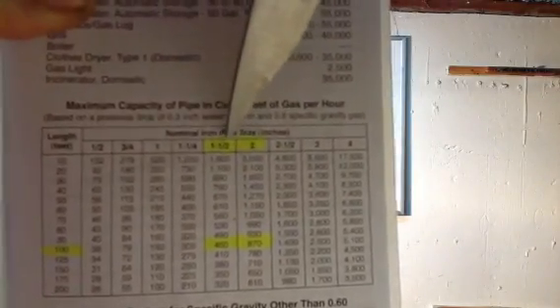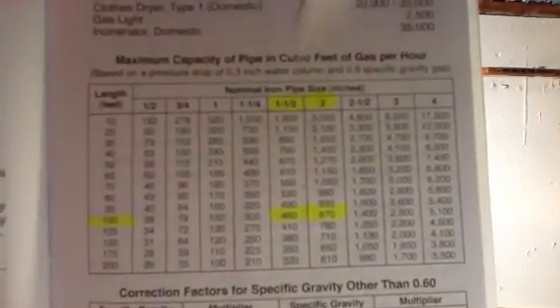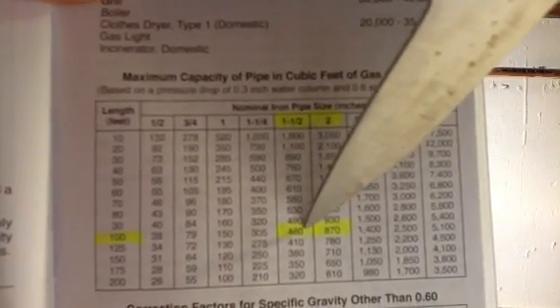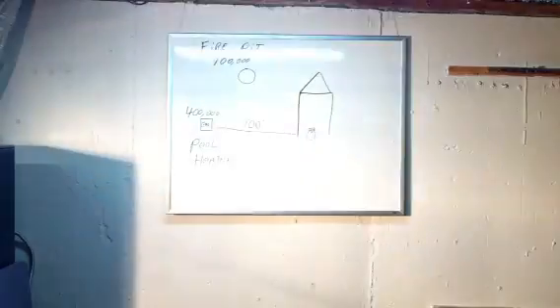I went down and I found 100 feet. I went all the way over and found 460,000 BTUs if I run inch and a half. Inch and a half will give me 460,000 BTUs at 100 feet. Well, that was okay for the pool heater.